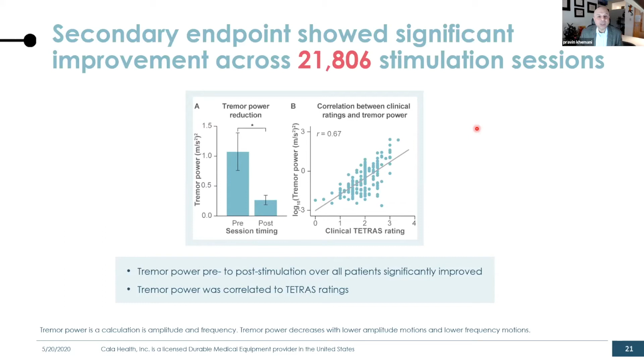So how is tremor power calculated? It is calculated through tremor acceleration. The stimulator, the Cala Trio stimulator, has accelerometers that measure tremor acceleration in 3 dimensions, X, Y, and Z. And that acceleration data is actually captured and it is converted to tremor power. This graph over here shows acceleration of the tremor in the Z-axis. This is the Y-axis and this is the X-axis. This raw data is collected and tremor power is calculated.